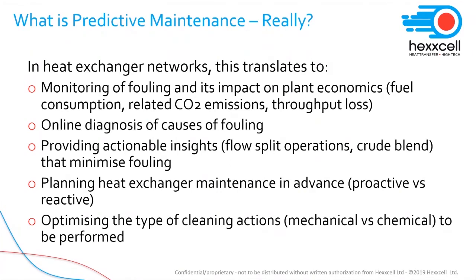But what does it mean really in heat exchanger networks? Well, predictive maintenance in heat exchanger networks involves the monitoring of fouling and its impact on plant economics, including fuel consumption, related CO2 emissions, throughput losses, etc. Online diagnosis of causes of fouling, providing actionable insights that minimize fouling, so operation of flow split, for example, or crude blend operations. Planning heat exchanger maintenance in advance, being proactive versus being reactive, and optimizing the type of cleaning actions to be performed. So being prescriptive on which type of action needs to be taken. So again, all these capabilities hinge on the ability of predicting fouling accurately as a function of operating condition, fluid composition, and time.